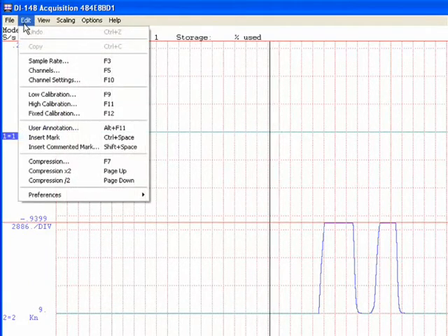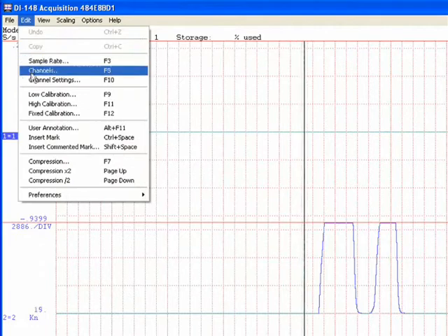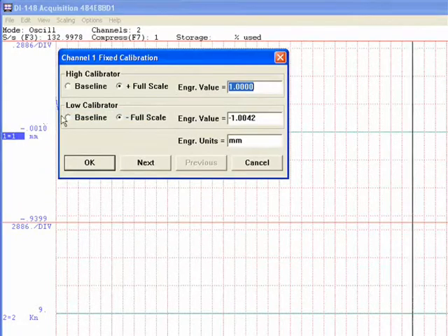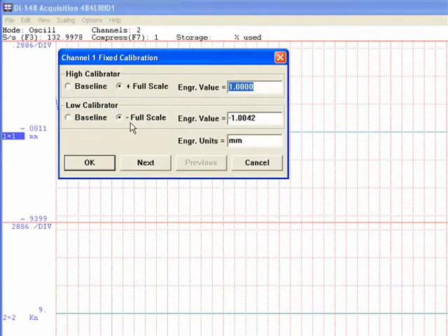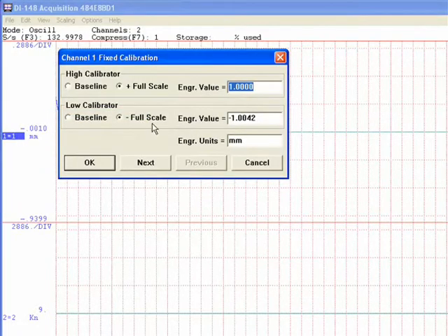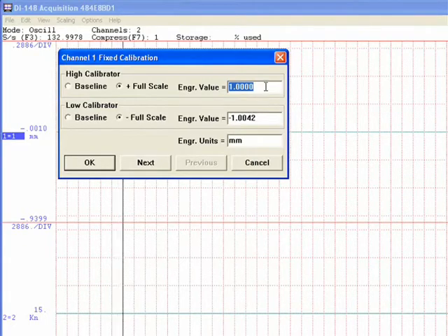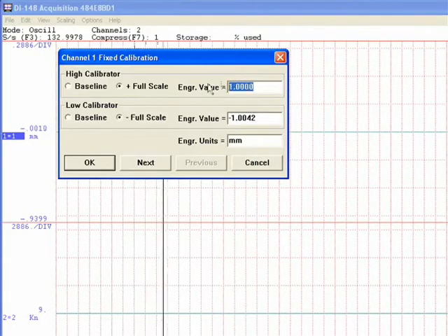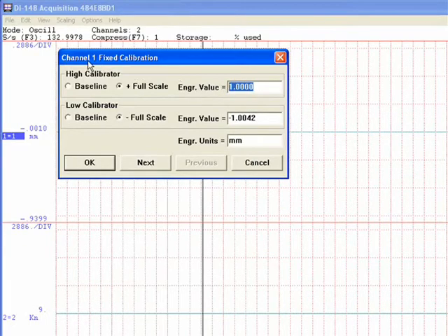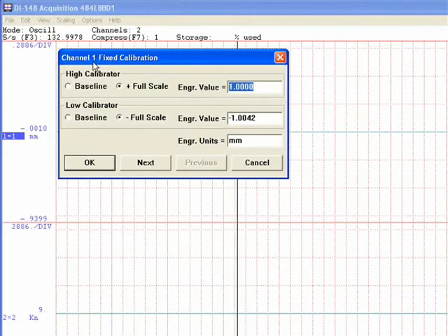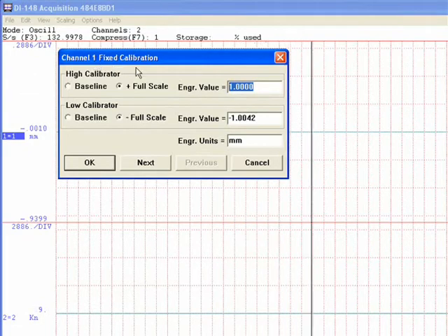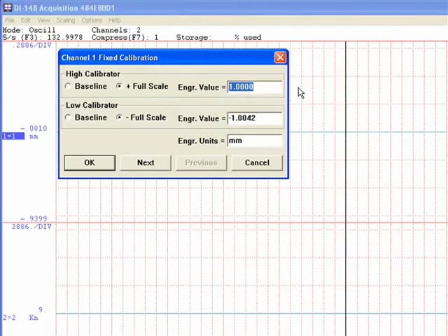Select edit, fixed calibration. You want to make sure they both say full scale. This is sensor number one, which should be your displacement transducer.